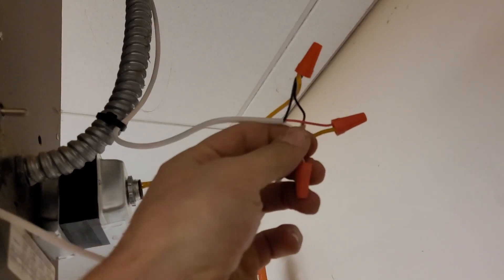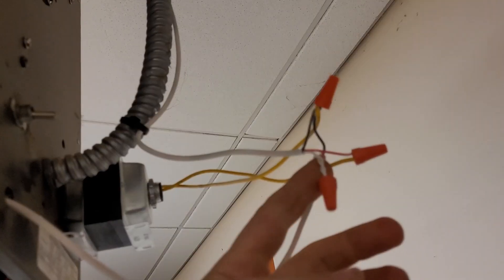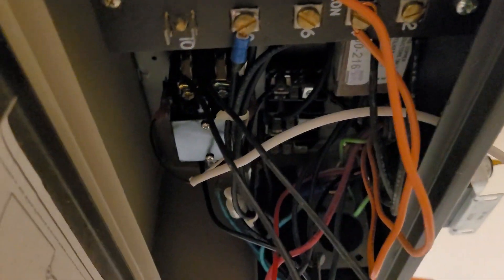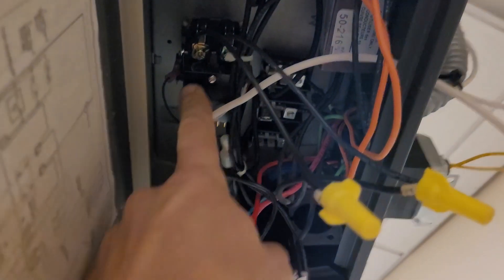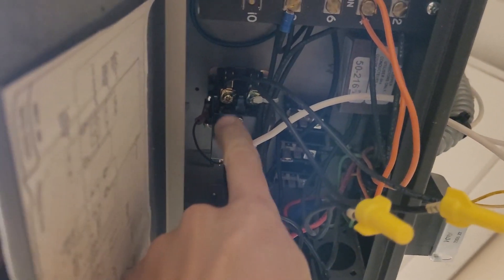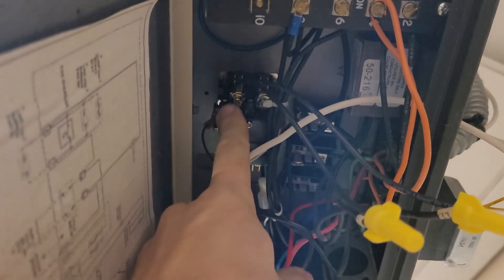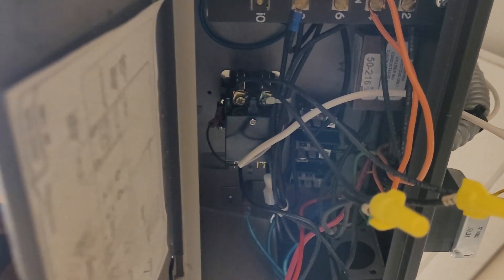That heat call goes in and I've also installed a contactor. The contactor breaks power going to the unit. It's a two pole contactor, and there are two legs of the 208 running in, so a two pole contactor was what I needed.